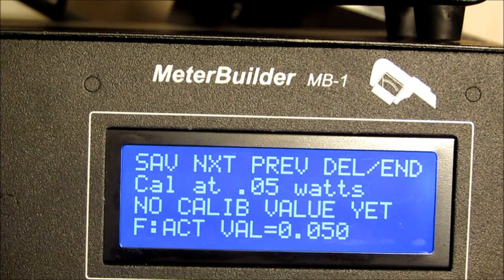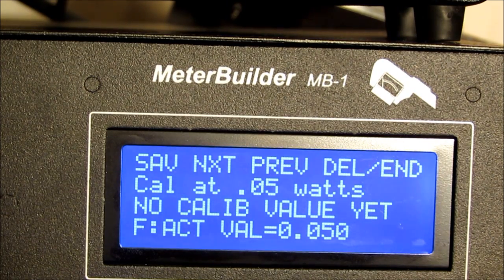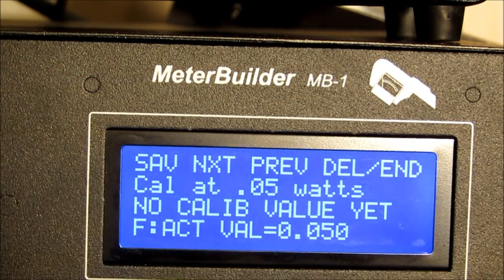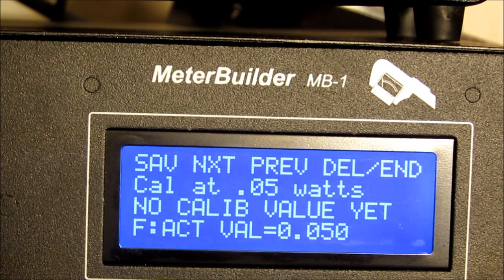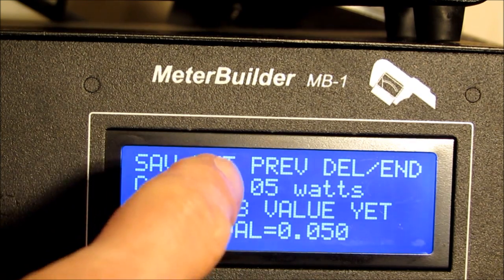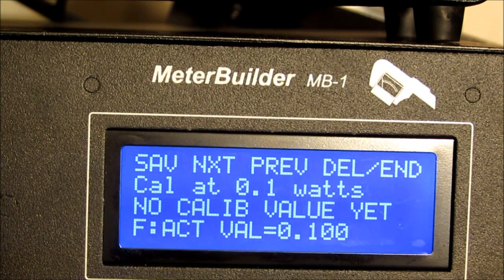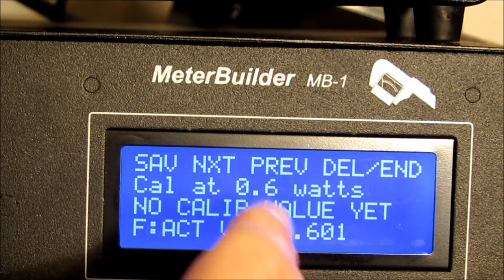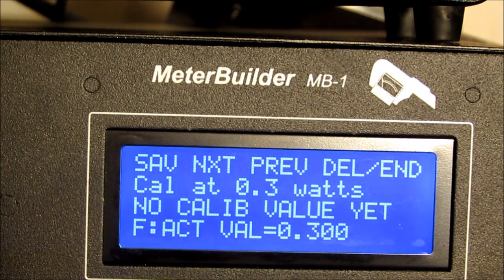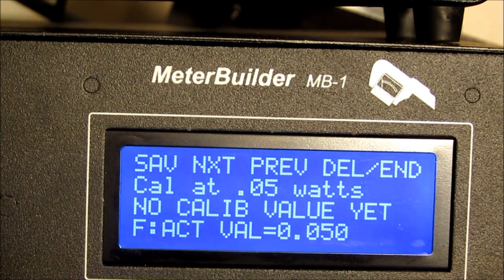Now, what we're going to see here is that the meter is going to run us through each of the possible calibration points and ask us if we want to perform a calibration at that point. The lowest point where we can calibrate is 0.05 watts. If I wanted to skip that and move up to the next available calibration point, I'd hit next. If I wanted to go back, I'd hit menu button 3. So 0.05 again is the lowest calibration point.